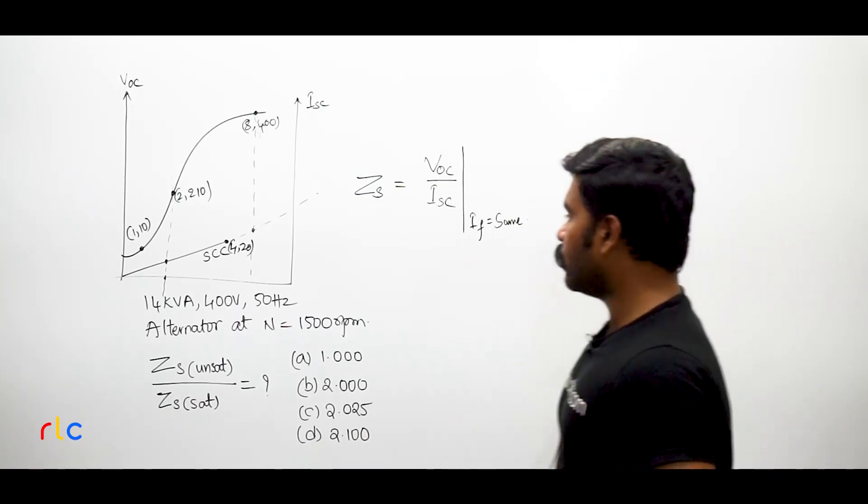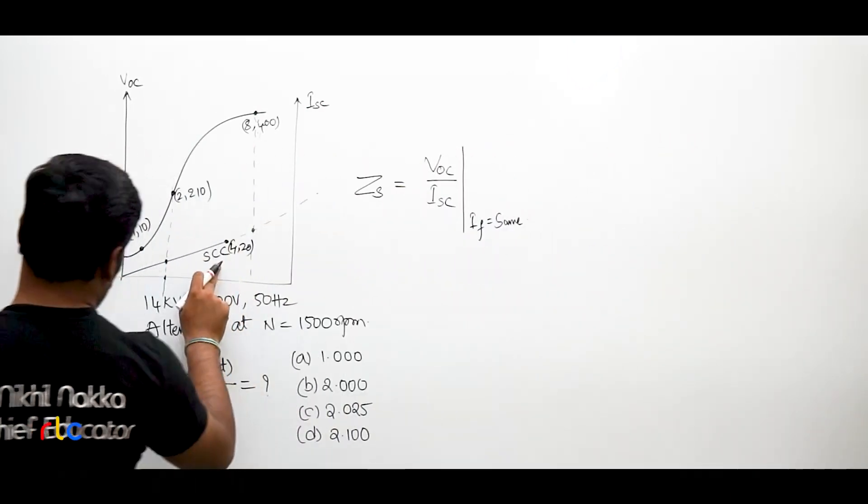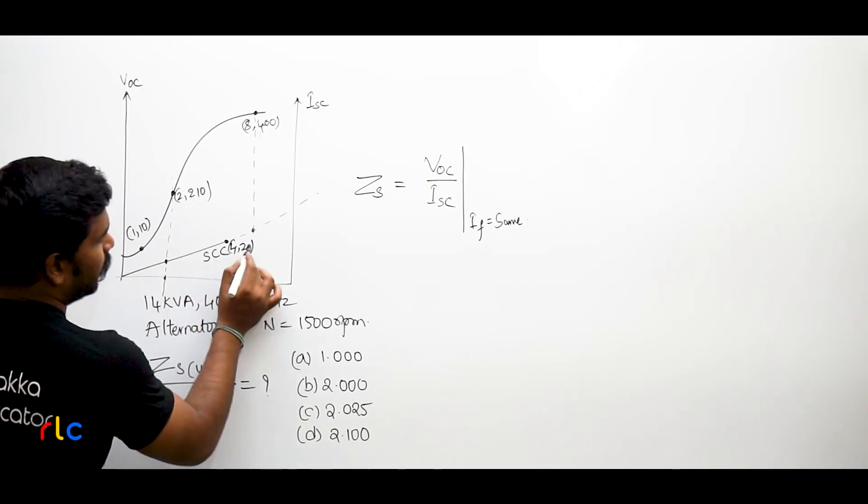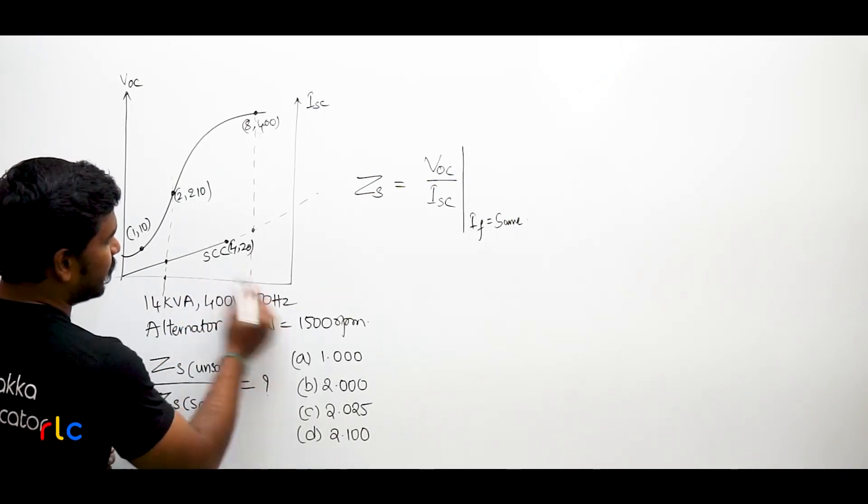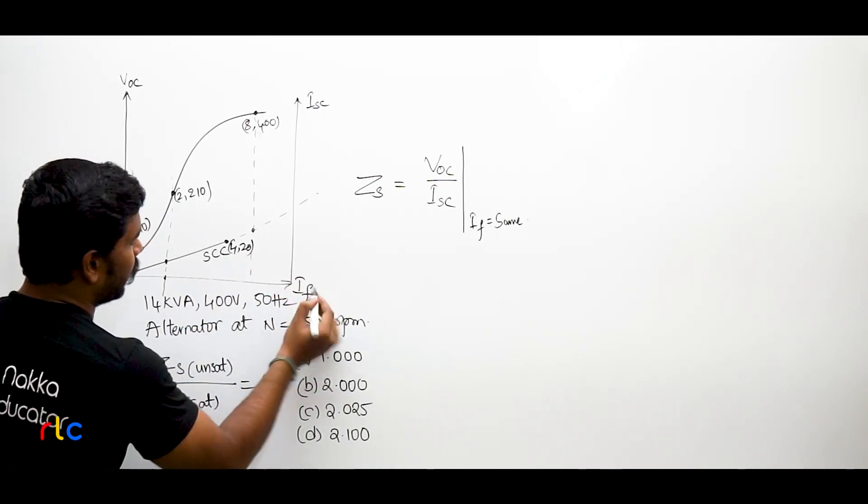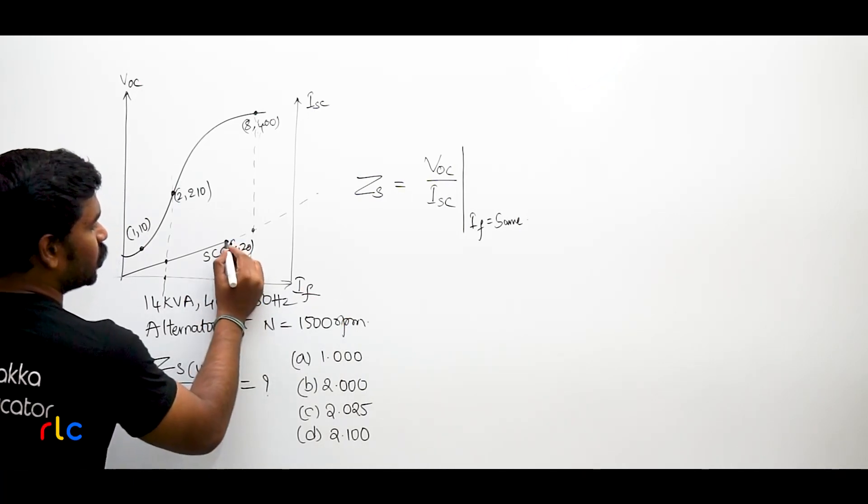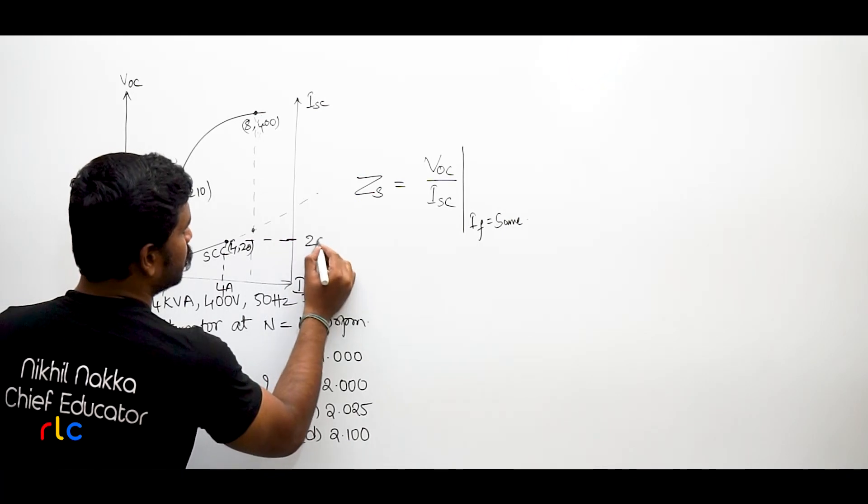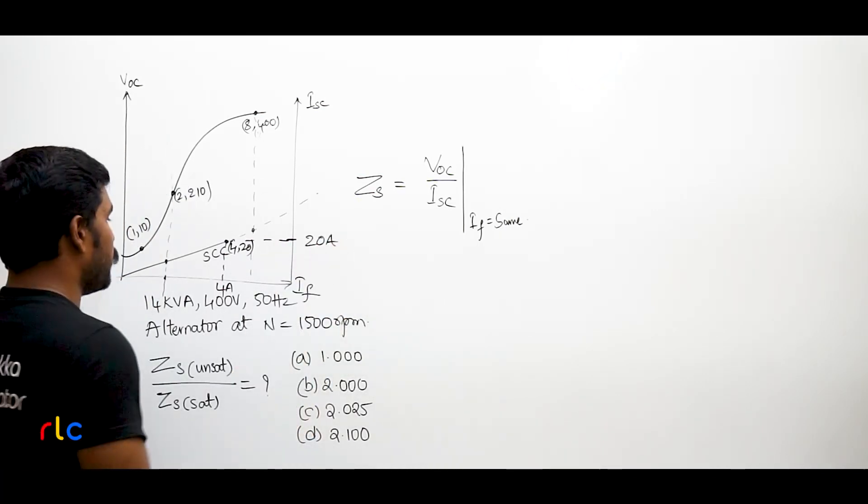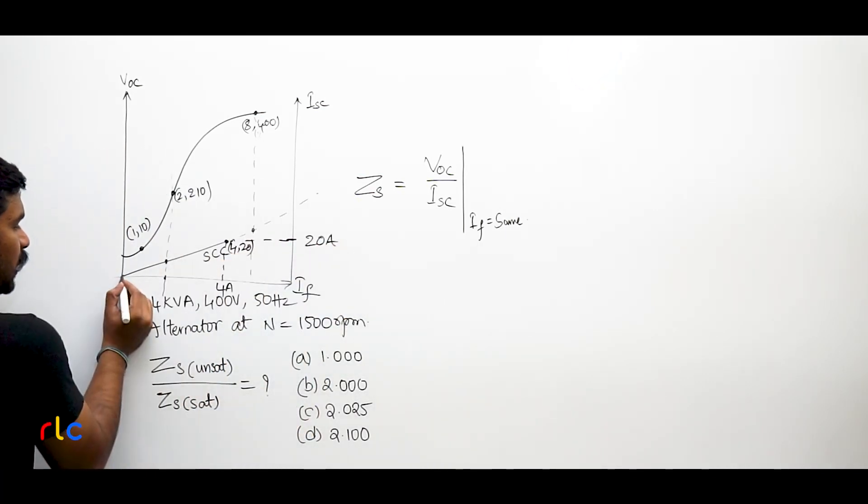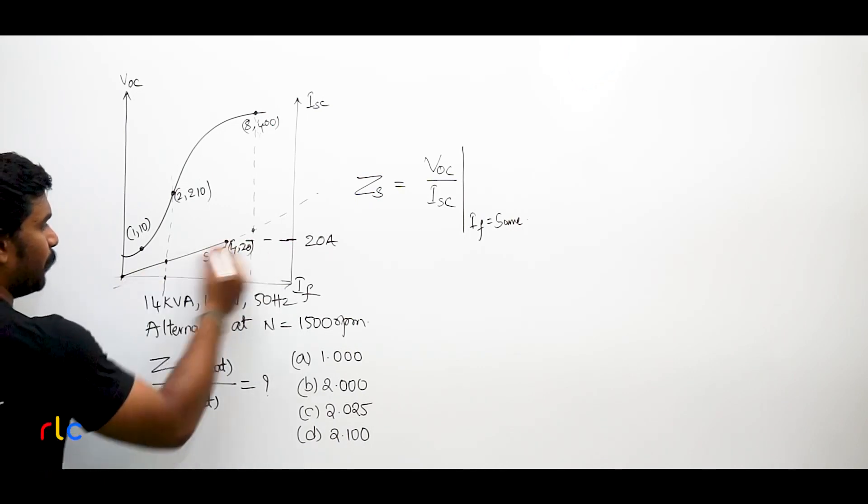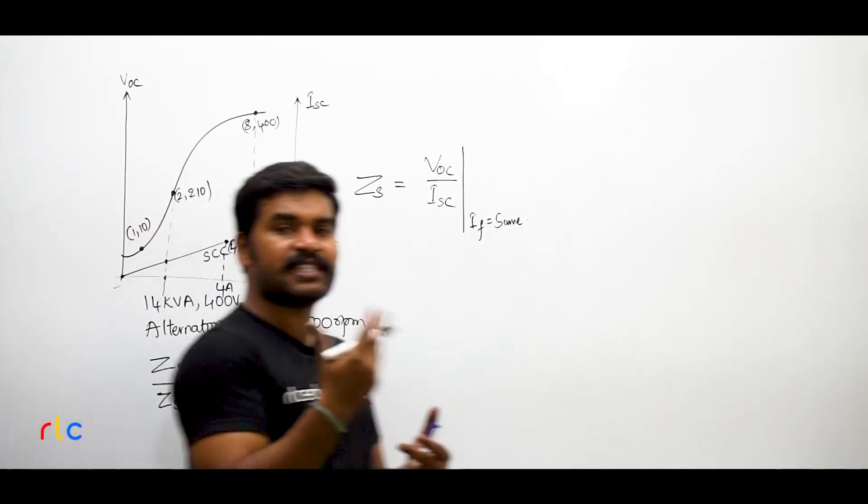So that is what we are going to do here. He says that according to the short circuit test 4 comma 20. 4 comma 20 means what is the X axis? X axis is the field current, that means at 4 Amperes of the field current the short circuit current is how much? 20 Amperes. And you see, what is the short circuit curve? The short circuit curve is nothing but a straight line passing through the origin, that means it is a linear graph.